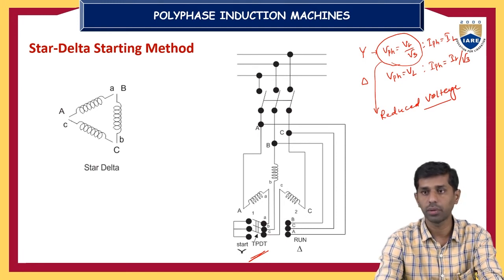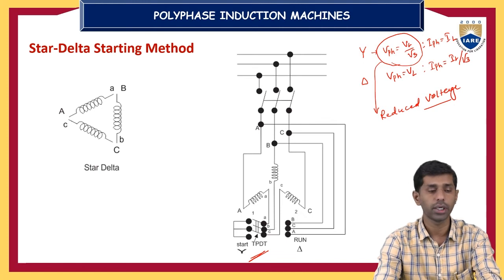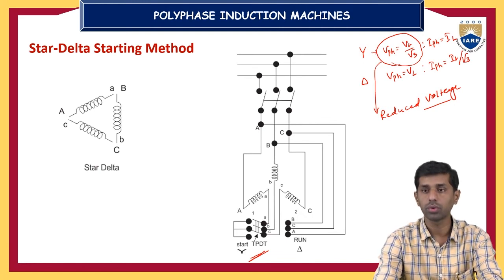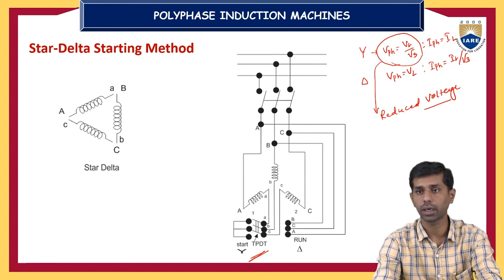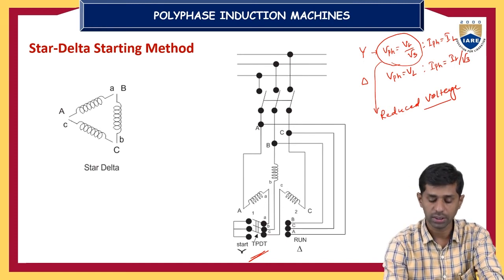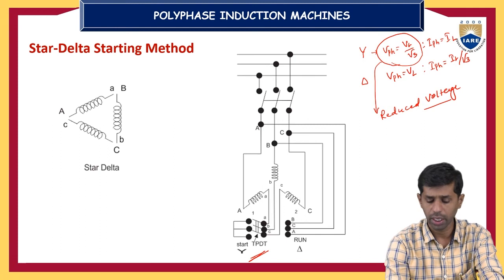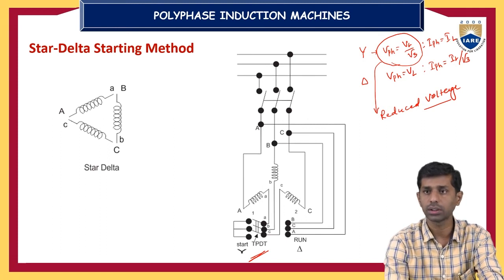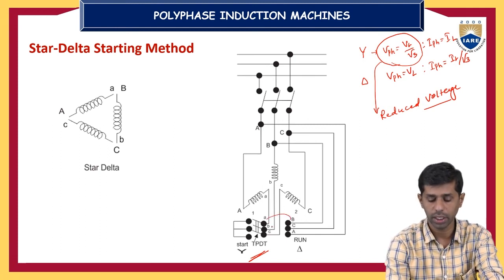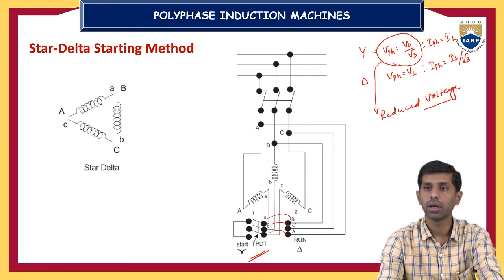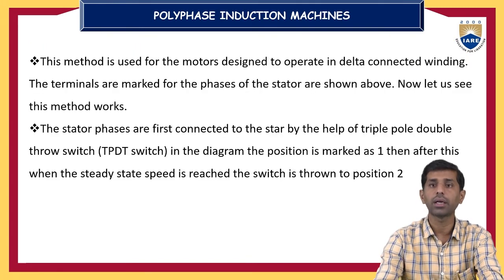Automatically, there will be a TPDT switch, a triple pole double throw switch. When it is started with the help of the triple pole double throw switch, it makes the stator winding star connected. Once it attains the normal operating speed, this triple pole double throw switch is switched to the delta connected network. So instead of connecting with A, B, C, it is now shifted to capital A, capital B and capital C. Now the stator winding becomes a delta connected winding under running condition.